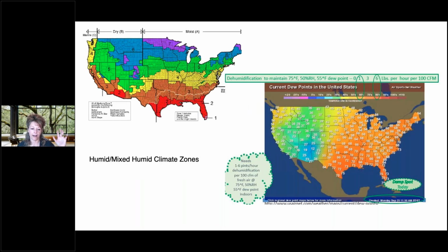So here's a dew point map in conjunction with our climate zone map. As you can see, where the moist area is, that A along the top there on our climate zone map correlates where we have higher dew points in our dew point map. This is a dew point map from late September. We've got 70-degree dew points in the Northeast all the way down to Texas and Florida. So we're probably not running a lot of air conditioning, especially in the Northeast. Probably partial load potentially down in Florida, because who knows, we're not sure what the temperature is, but I guarantee it's probably not peak load. But we've got the same amount of moisture in the air. So that's the challenge we're facing as an industry, controlling the moisture when our AC is not running.